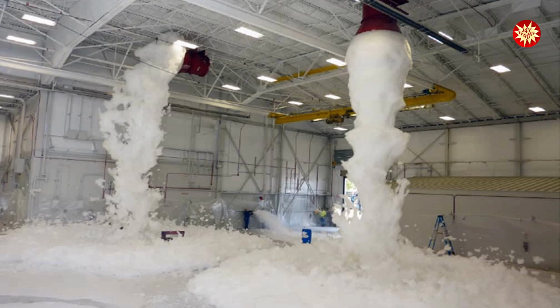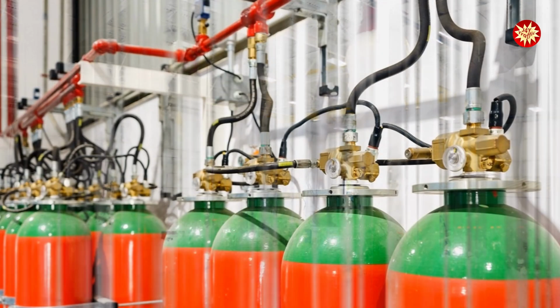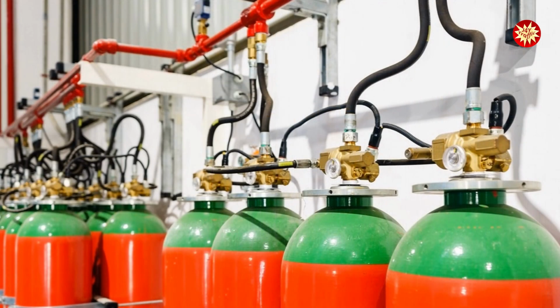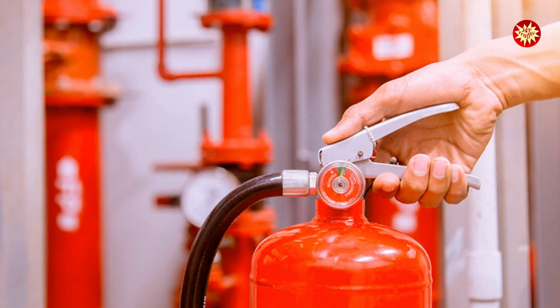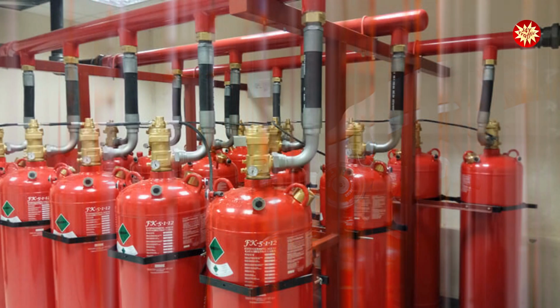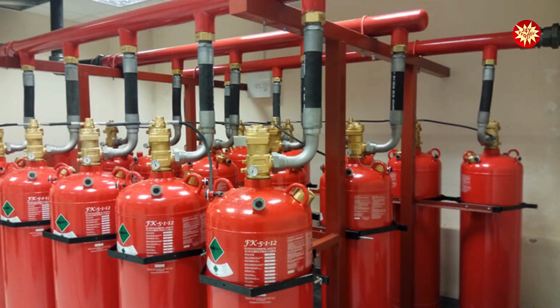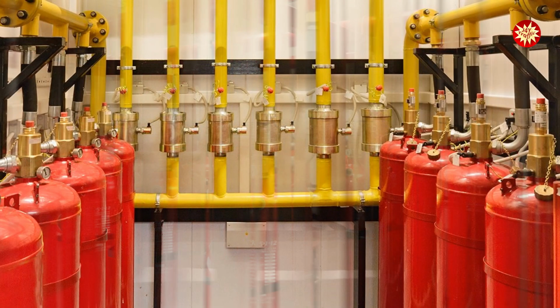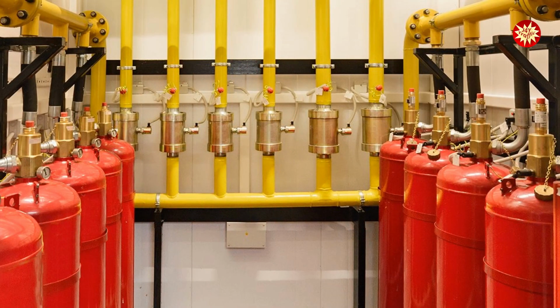One common type of fire suppression system uses clean agents. These agents are gaseous substances that are electrically non-conductive and leave no residue upon evaporation. They work by interrupting the chemical reaction that sustains a fire. Clean agent systems are often used in areas where water damage would be catastrophic, such as data centers and server rooms. Another type of fire suppression system uses foam.